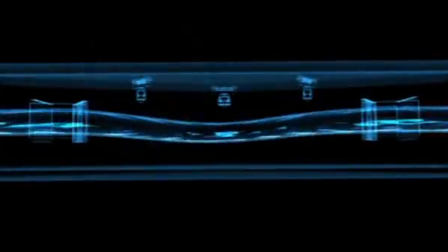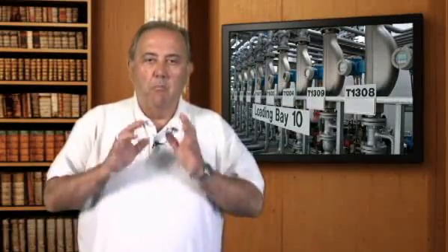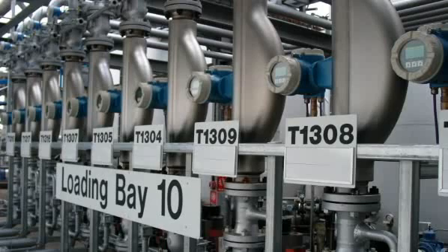A Coriolis mass flow meter can also be used to independently measure density and volume of the fluid passing through it. At rest, the resonant frequency of the tube changes as the density of the fluid changes. This can be used to determine the density of the moving fluid by dividing the mass by the known volume of fluid in the tube. Dividing mass flow by the density so derived gives us volumetric flow. Because Coriolis flow meters are directly measuring mass to a high level of precision, they are very highly accurate in measuring flow and density. This has made them very commonly used in custody transfer applications.